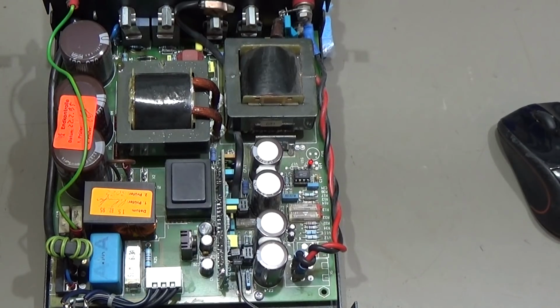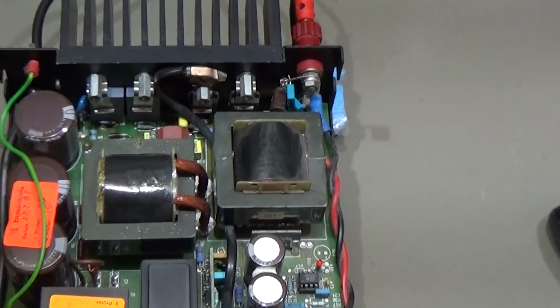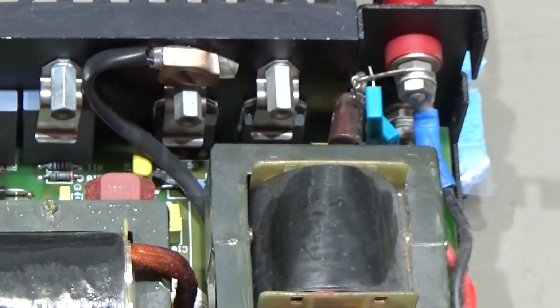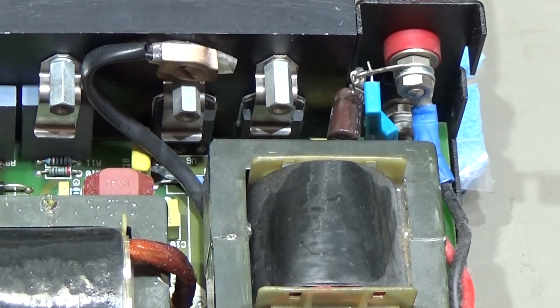The controller board has different so-called error amplifiers on the board, and they control different incidents, such as what we can see here, for instance: a temperature sensor which controls the heatsink temperature, and when the temperature rises a certain level, the error amplifier gets the information and switches off our oscillation.